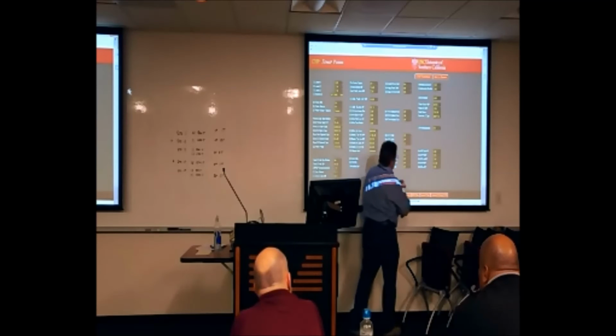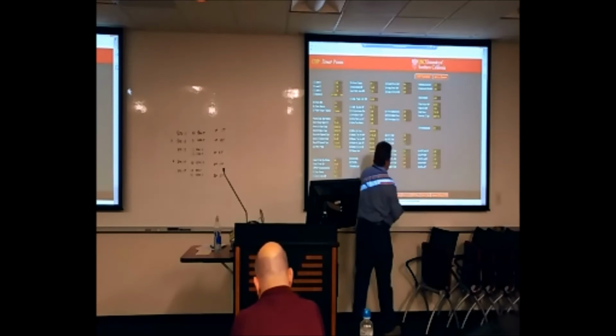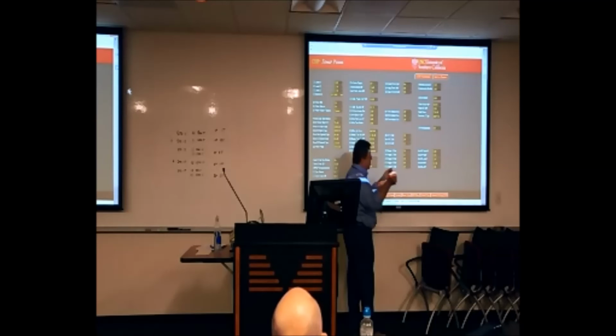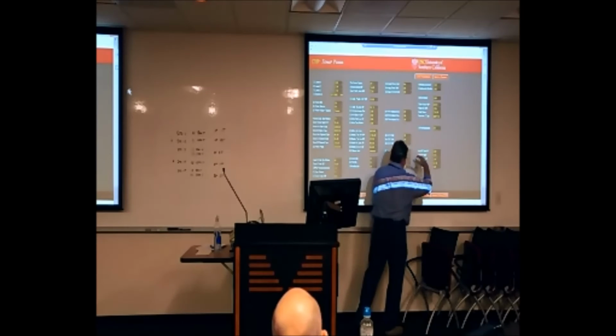What we do is we're looking to control a delta T across the condenser barrel of about 10. So we allow it to go down as low as 8 or as high as 12, looking to really settle out around 10. As we go to the low set point, in other words, as we start creeping down to an 8-degree delta T, we want to slow the pumps down to grow that delta T. So we look to have a condenser water DP set point, the differential pressure across the condenser barrel, of 2.5 psi. And the pumps will slow down to control to that 2.5 psi.